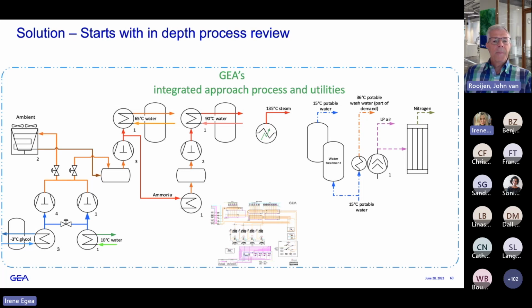We have introduced a 10-degree water system for HVAC applications, and now with a total of 4+1 piston compressors, we are able to reject all the heat required. Part is still, if not used by the heat pumps, provided to the ambient, but as indicated, at least around 50% is now captured to generate 65-degree water and 90-degree water. GEA also applied the other utilities like electrical steam boilers, but also potable water treatment, compressed air plant, and nitrogen generation. And there we also introduced a heat recovery from the air compressors to preheat all the water which is required on the total plant.